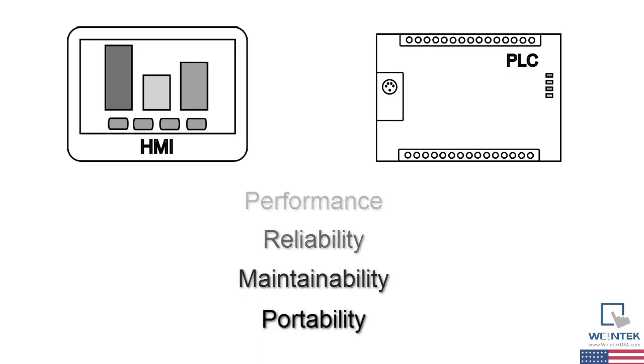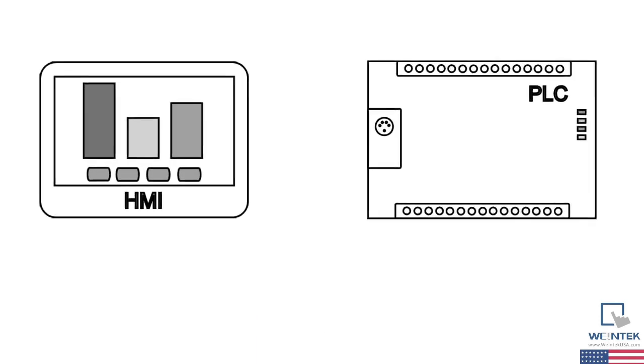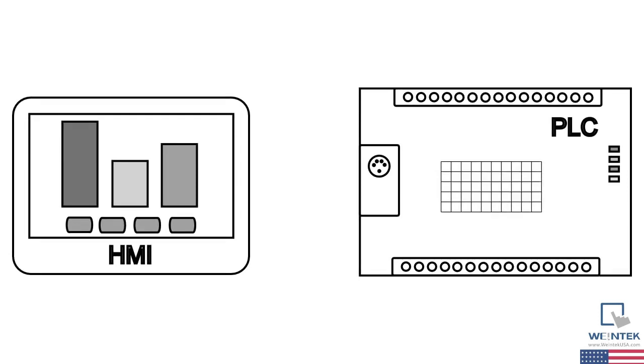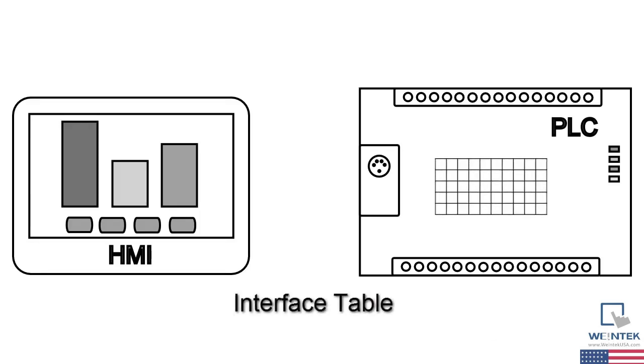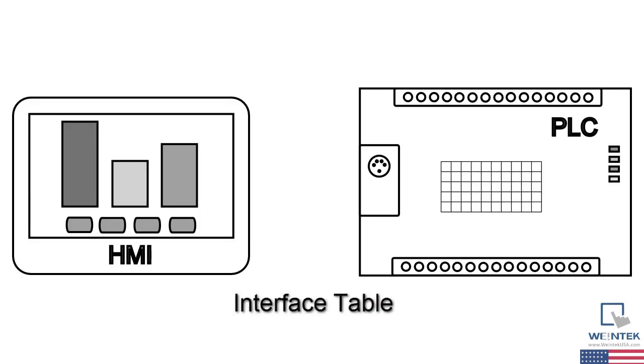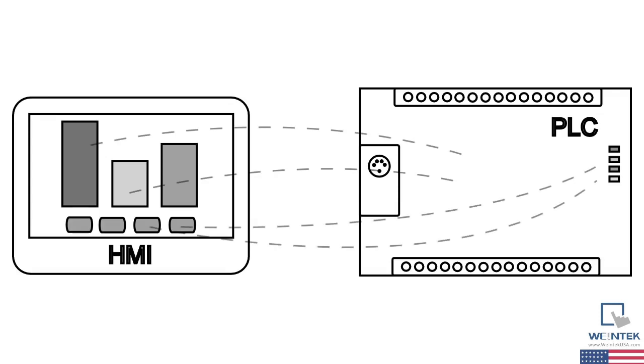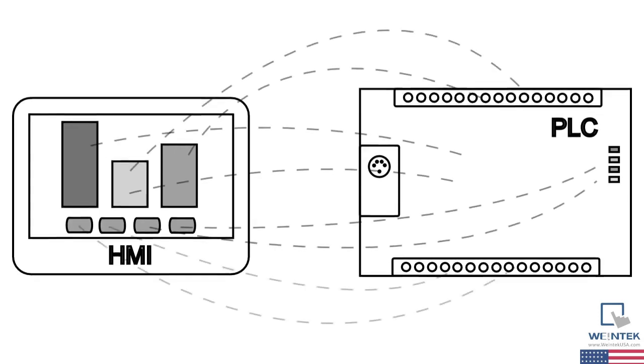The basic practice we'll be discussing is setting aside a block of standard memory in the PLC to serve as an interface between the PLC and the HMI. For reference in this video, we'll call it an interface table. This is in contrast to a more ad-hoc approach of just pointing the HMI objects directly at whatever data and I.O. in the PLC we're interested in - some memory here, some control registers there, some inputs, some outputs, and so forth.